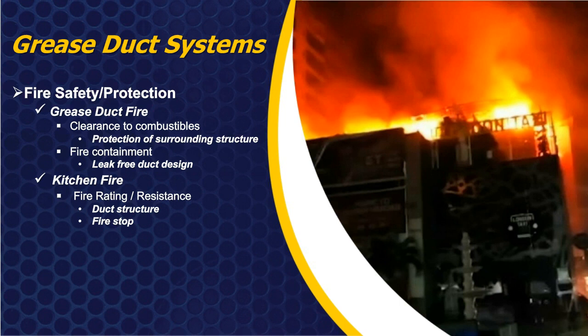The second part of fire safety and protection is in the event we have a kitchen fire, so something else in the kitchen starts on fire. Maybe it is the fryer or the grill. What we don't want the grease duct system to do is allow that fire in the kitchen area to go through the entire building. So with the fire resistance rating, we're paying attention to the structural integrity of the ductwork itself, and then the fire stop system as it penetrates through a ceiling or into a chase or surrounding areas of the building.